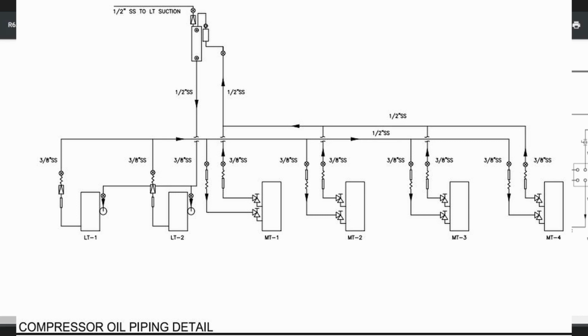Okay. So we put a cap tube in there so that there's an intermediate pressure, and both machines can pump into that line. Gotcha. Then the line goes over to the crankcase of the medium temp and goes through another cap tube, which actually creates the intermediate pressure, and then it flows into the 4 medium temp compressors. Whether they're running or not, even if it's sitting there off, oil is still flowing into it. Oh, wow. Okay. But then when it gets to half a sight glass in that medium temp compressor that's not running, it has to flow back to the reservoir.